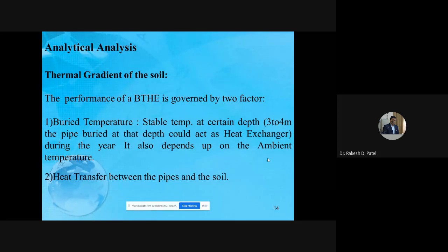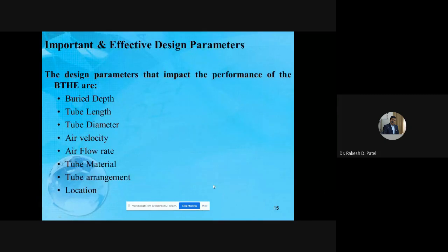So what is the buried temperature? The stable temperature at a certain depth. As per the geographical condition, it may vary from 3 to 5 meter. Specifically in the Anand region, it is at 3.5 meter. The pipe buried at this depth could act as a heat exchanger. During the year, it also depends on the ambient temperature, so ambient temperature plays a very important role for the buried temperature. Second, the heat transfer between pipe and soil, which is an important and effective design parameter of the heat exchanger.